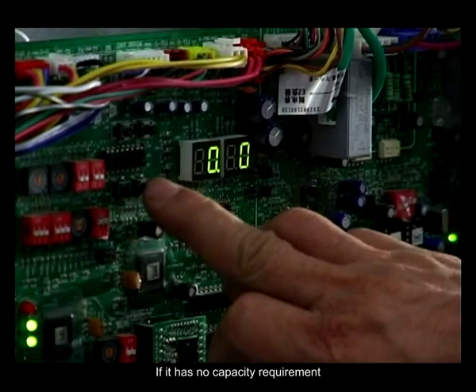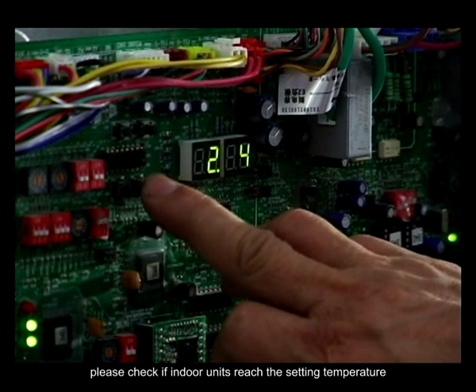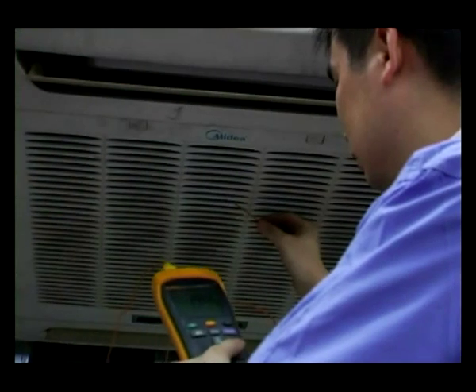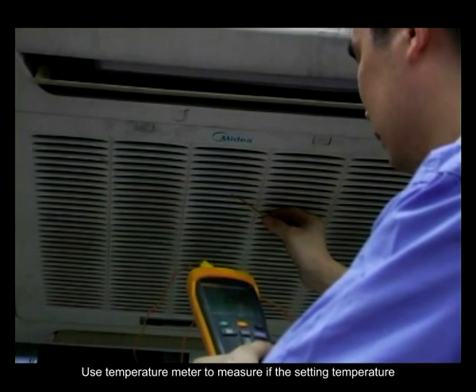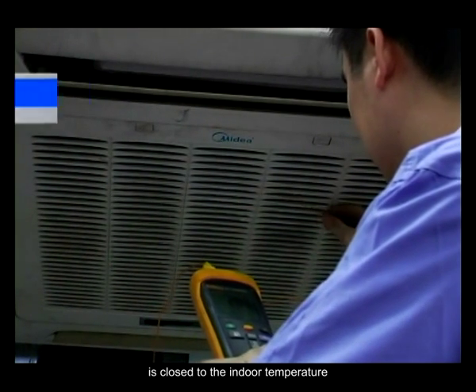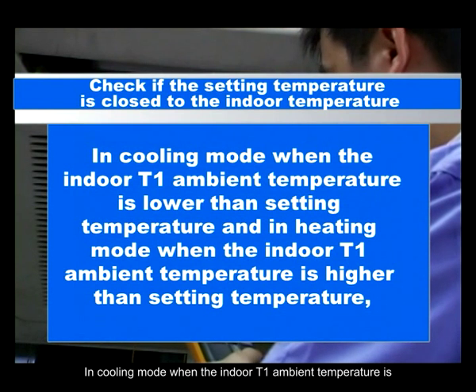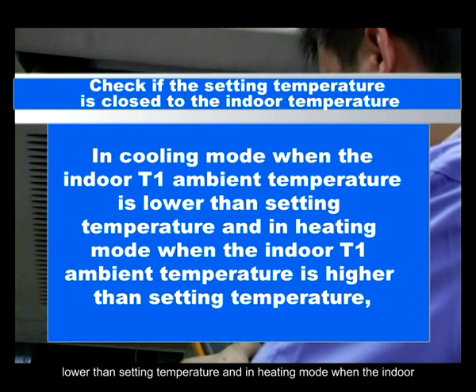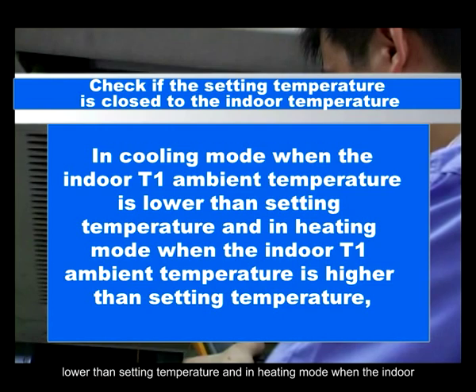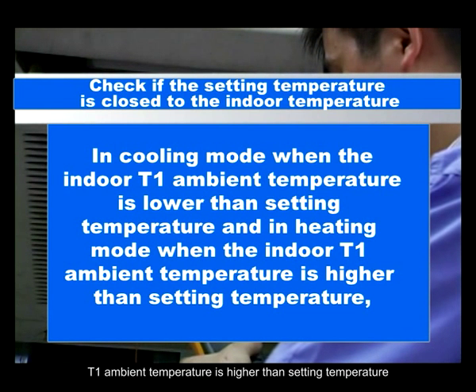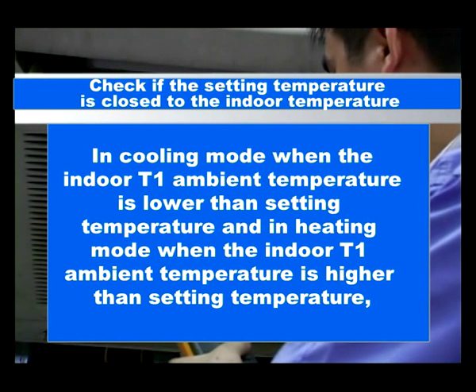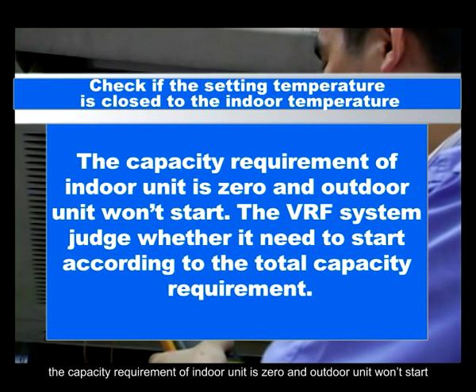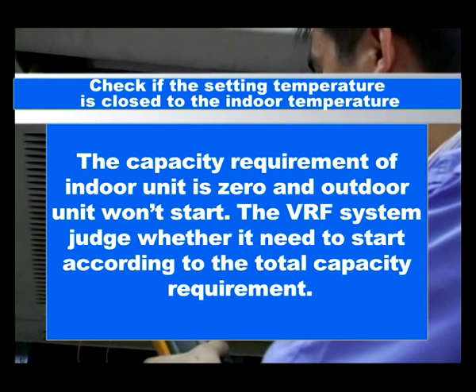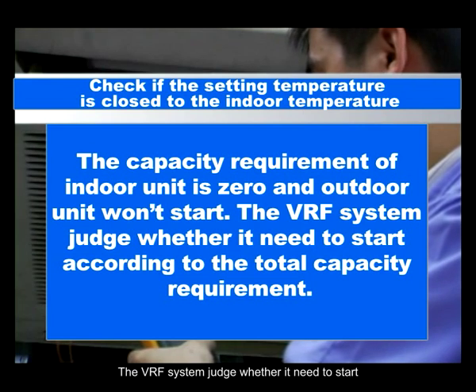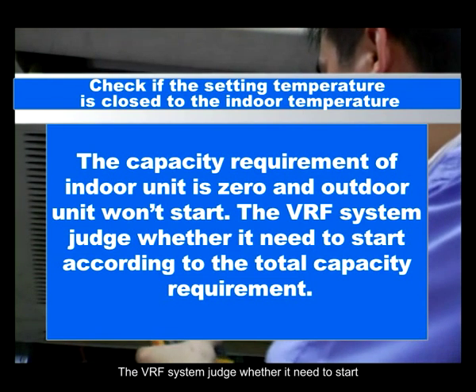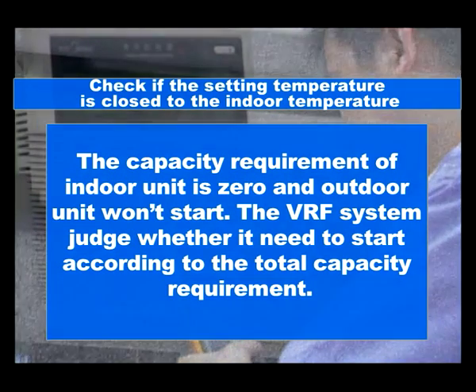If there is no capacity requirement, check if the indoor units reach the setting temperature. Use a temperature meter to measure if the setting temperature is close to the indoor temperature. In cooling mode, when the indoor T1 ambient temperature is lower than the setting temperature, and in heating mode, when it is higher than the setting temperature, the capacity requirement of the indoor unit is 0, and the outdoor unit won't start. The VRF system judges whether it needs to start according to the total capacity requirement.